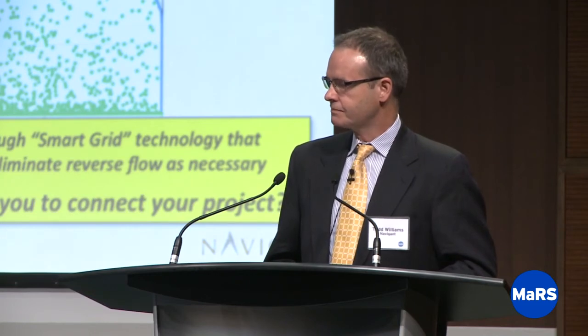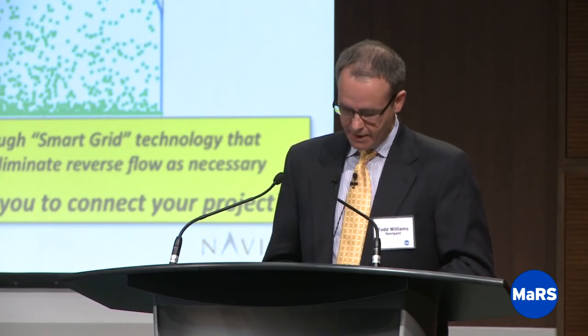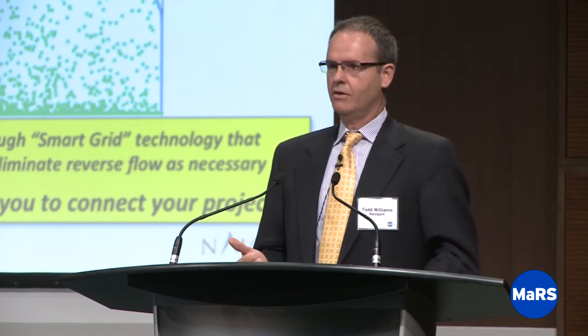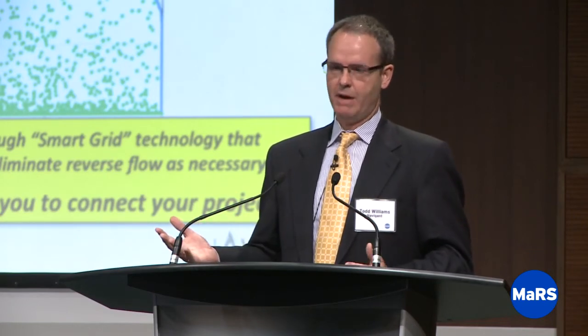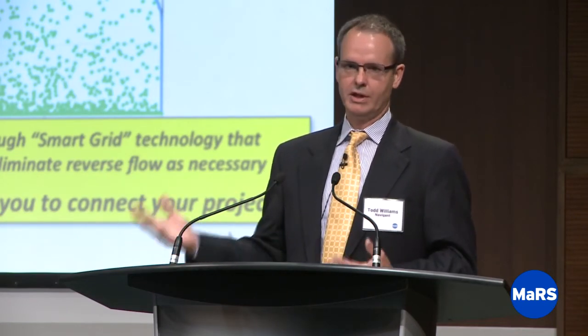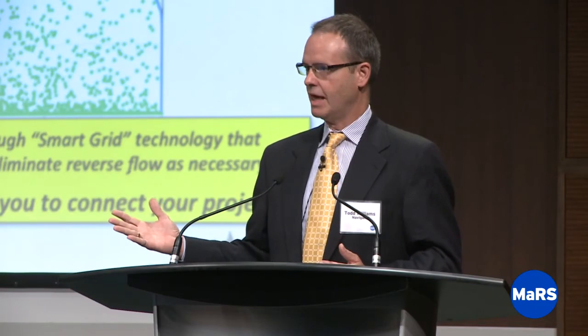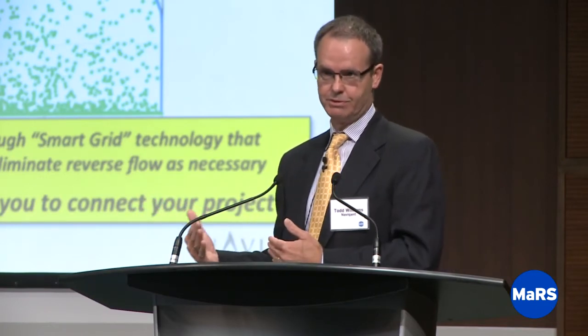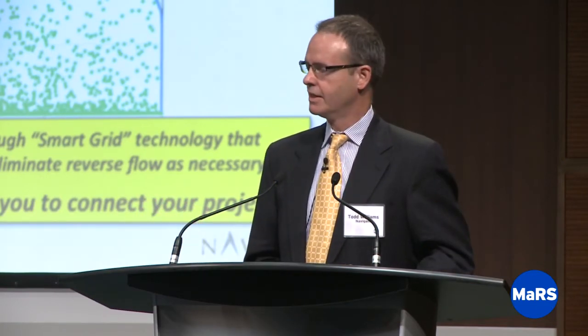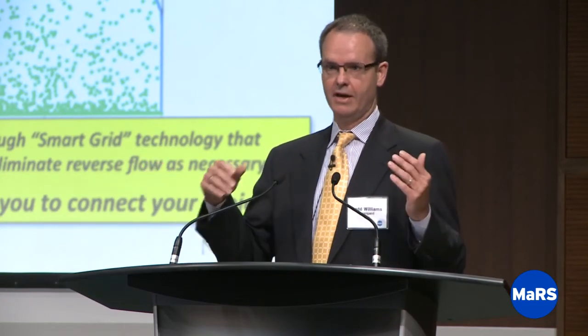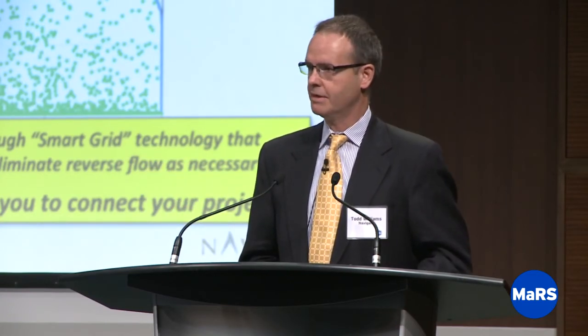Now, in order to do that though, I think from a safety perspective, if we had a perfect system, we'd look at that and we'd shut down the PV at that point, or we'd dial it back to be just below the transformer loading. Then the system would still be safe, and I'd have a heck of a lot more PV capacity on that line.